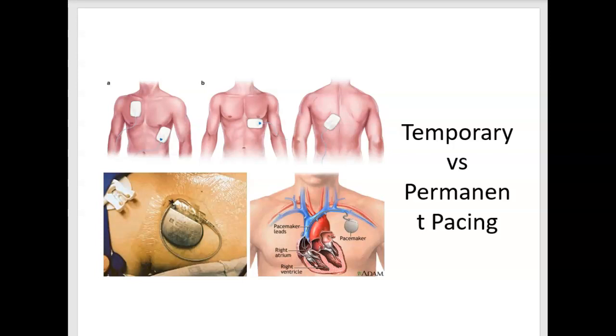When a pacing stimulus is delivered to the heart, a spike or pacemaker artifact is seen on the monitor or ECG strip. The spike should be followed by evidence of depolarization such as a P wave or QRS complex. The pattern is referred to as a capture. So on the ECG strip, you'll see a marking indicating that the pacemaker has fired. And then after that, if the pacer has captured, you would see either the P or QRS following immediately after the pacer spike. If it does not capture, then you'd see the mark indicating the pacer has sent out an impulse, but nothing behind it, and that would be termed that it has not captured.